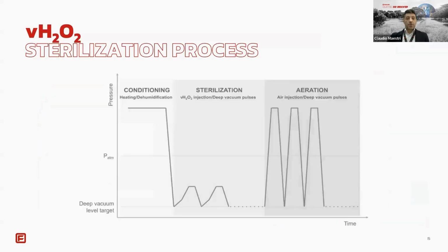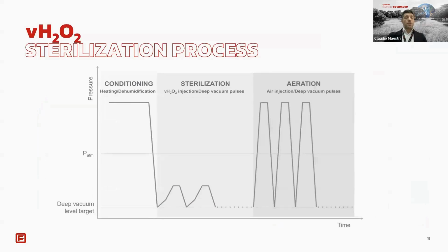About the process, as we can see here, the main phases of a typical H2O2 deep vacuum autoclave sterilization are, first, the autoclave preparation, which means preheating and process checks. The chamber is warmed up and the system conditions like vacuum and H2O2 supply are checked. And then deep vacuum and loading condition. Air is evacuated from the chamber to achieve the deep vacuum, improving H2O2 distribution around the load.